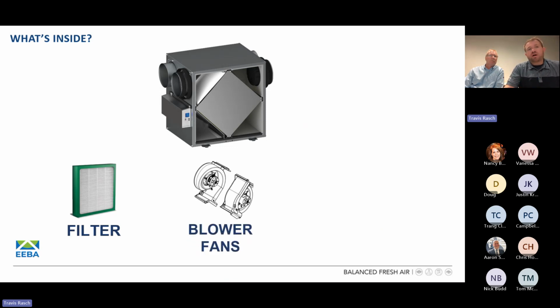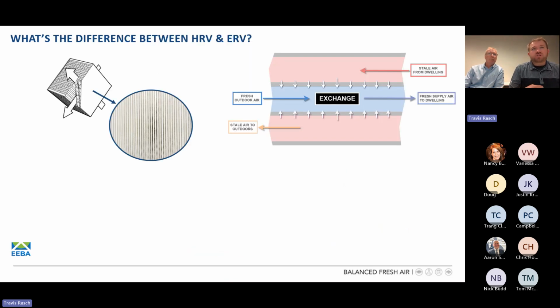Once we get that outdoor air in, we're going to use blower fan motors. Basically, we've got to draw that air in from the outside. We've got to draw air from the inside of the building and make sure that we're moving those airflows consistently and at the same CFM. These airflows pass through what's called a recovery core. That's the cube-shaped thing you see in the middle there. That is our recovery core. Inside our recovery core, you're going to see there are thousands of these little air channels.